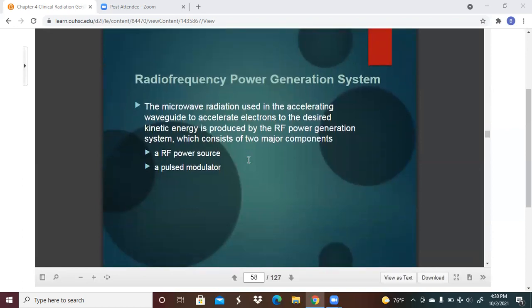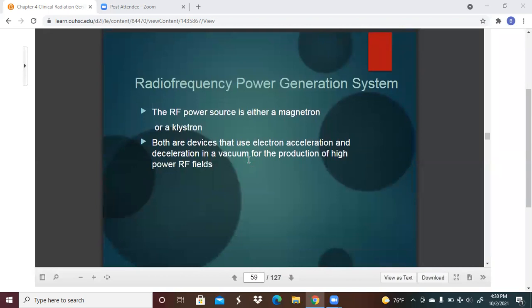So the radio frequency power generation system: the microwave radiation used in the accelerating waveguide to accelerate electrons to the desired kinetic energy is produced by the RF power generation system, which consists of 2 major components. You've got an RF power source and a pulsed modulator. The RF power source is either a magnetron or a Klystron. Both are devices that use electron acceleration and deceleration in a vacuum for the production of high power RF fields.